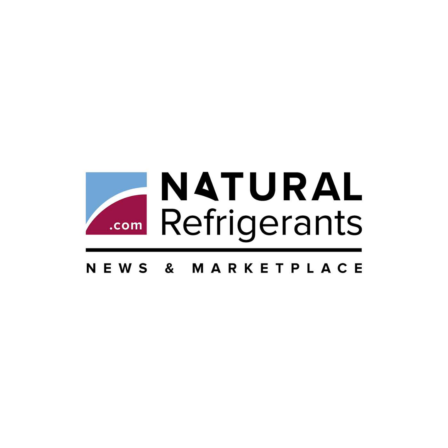Going CO2. As part of its climate initiative, Target plans to convert all of its stores to CO2 refrigeration by 2040. As of early 2025, Target operated 1,989 stores across the U.S., ranging in size from small format stores covering several thousand square feet to large stores spanning 200,000 square feet, 18,580 square meters. The panel pilot studies conducted by Target focused on reducing transcritical CO2 operation in conjunction with adiabatic gas coolers. We've tested the panels throughout the U.S. and we are seeing positive results in all locations, Holzschuh said.